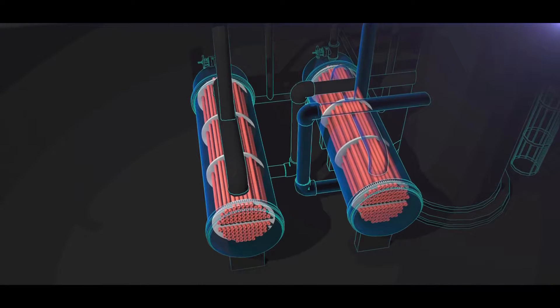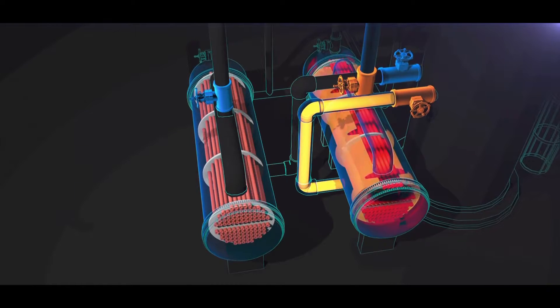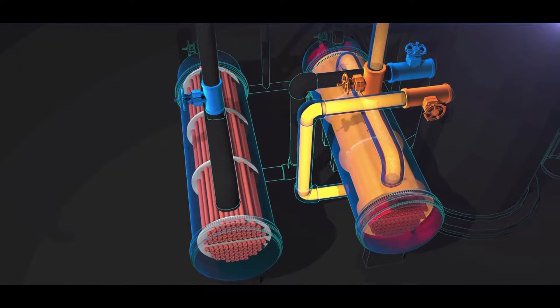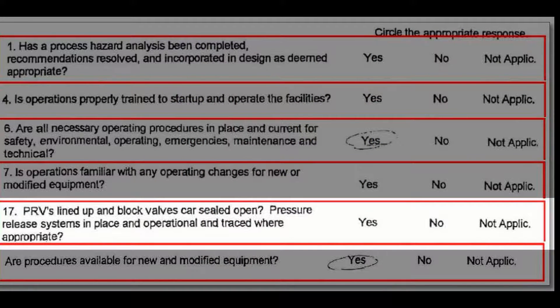After the 2001 re-boiler valve installation, Williams also performed a pre-startup safety review (PSSR), as required by regulations. But the CSB found that reviewers did not respond to key process safety questions on the form. One of those questions asked: 'Are pressure relief systems in place and operational?' That answer was left blank. Even though the PSSR document was incomplete, management approved the form, and the re-boilers were put into service without adequate overpressure protection.